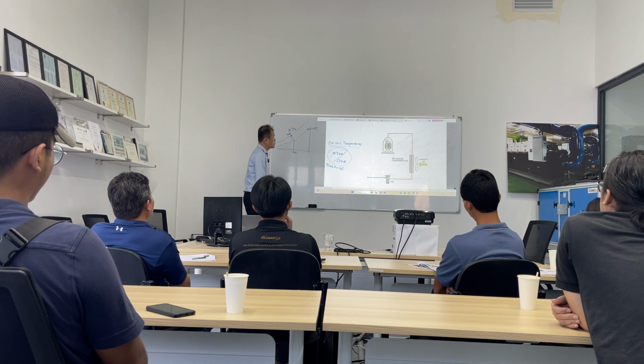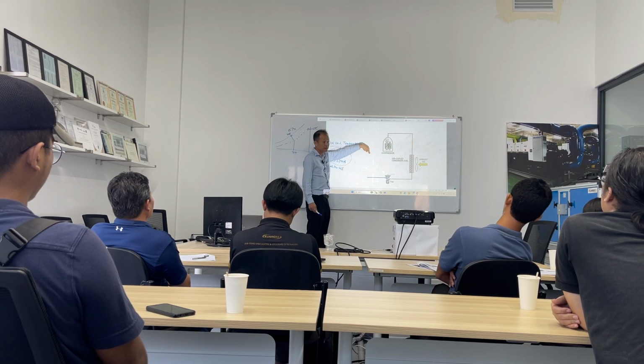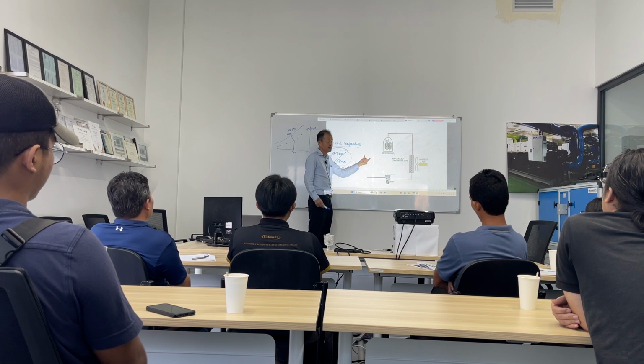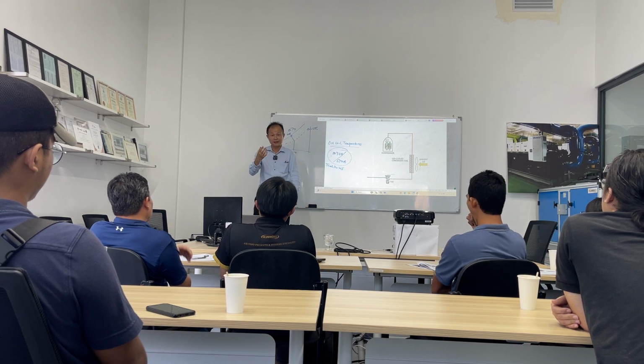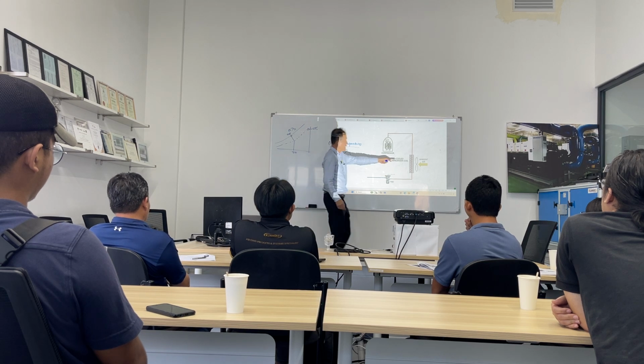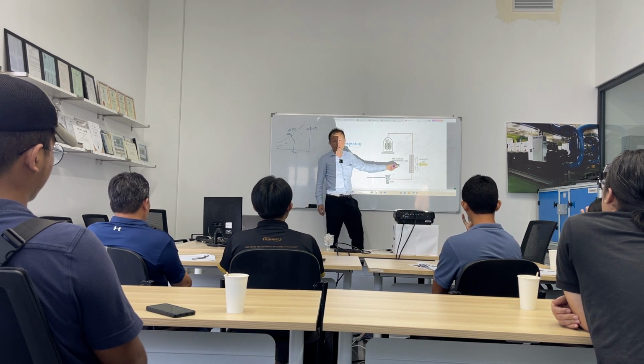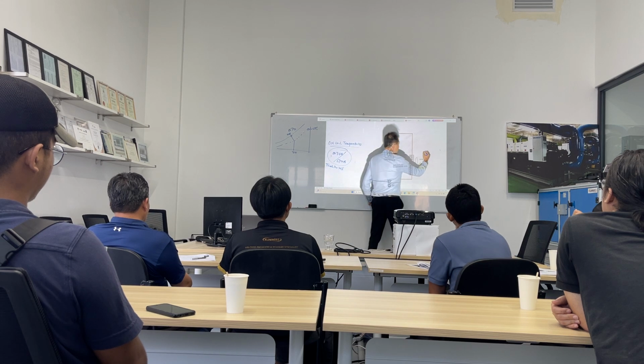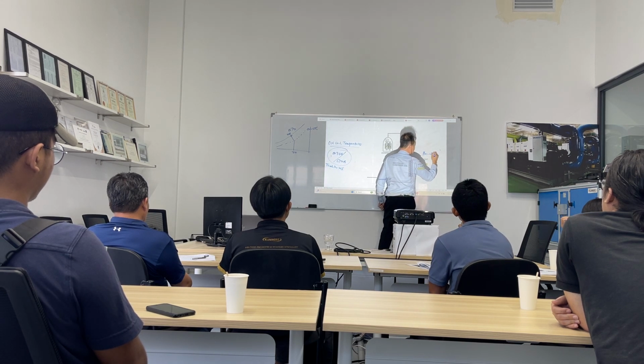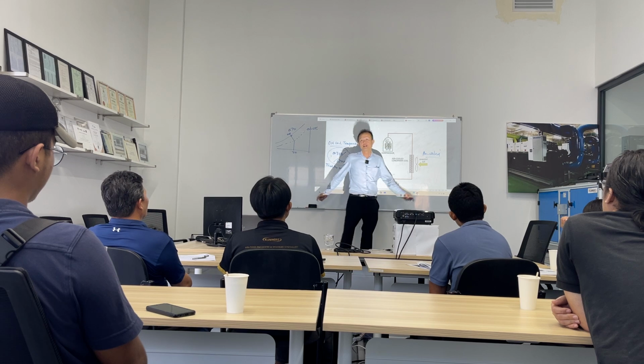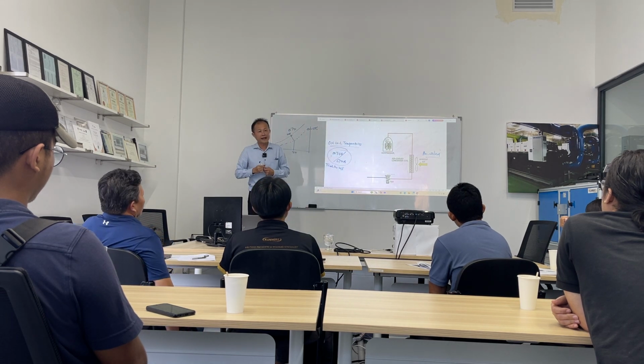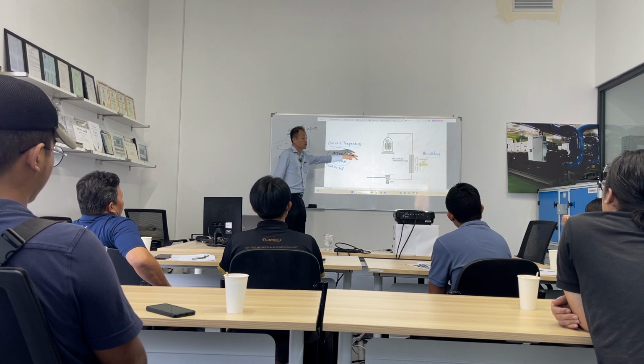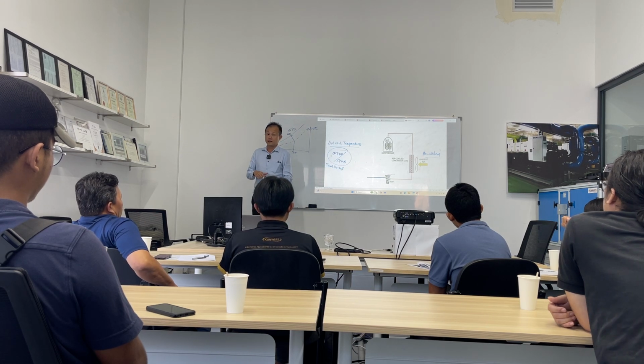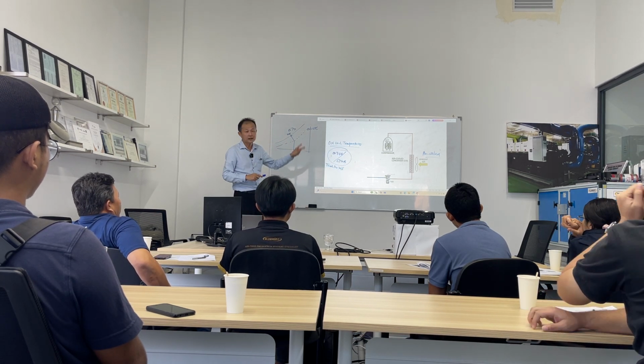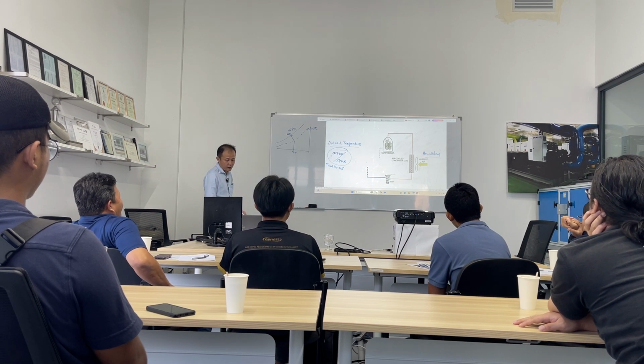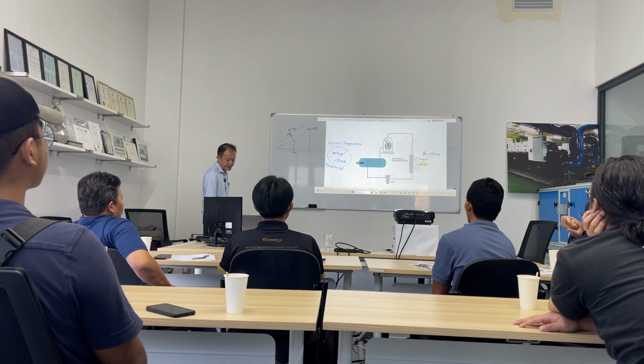Okay, just now I was talking about the DX system, where you have direct expansion, the refrigerant directly cooling the air, the direct expansion system. So now the condenser is cooled by air, it's called air cooled. This is called air cooled already. Air cooled system, okay? Because the air is used to extract the heat from the refrigerant circulating through the condenser coil.